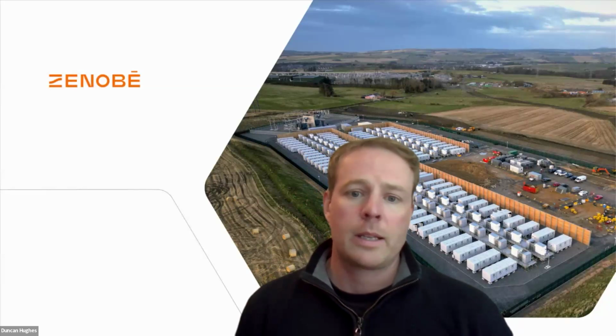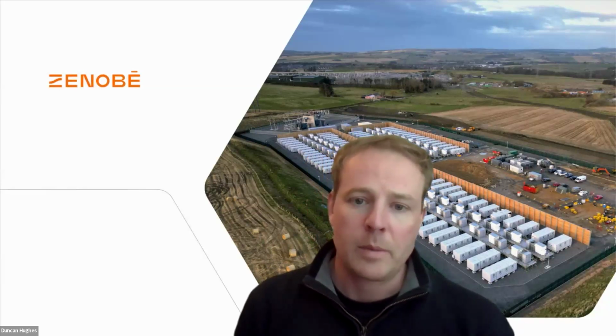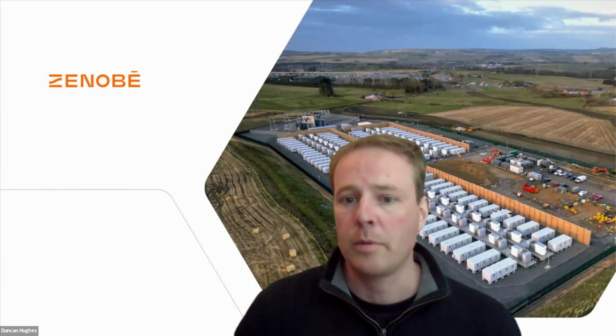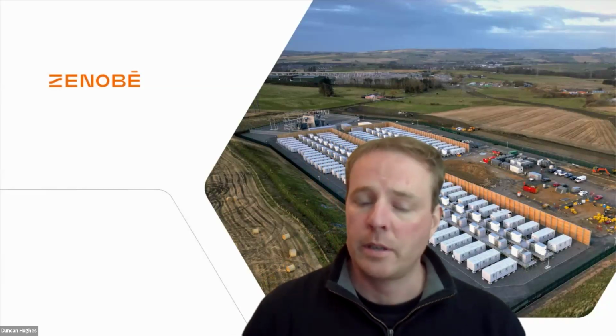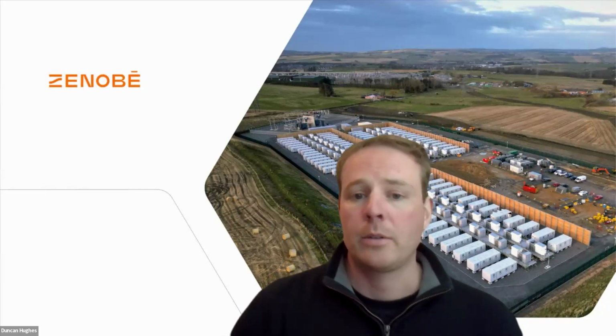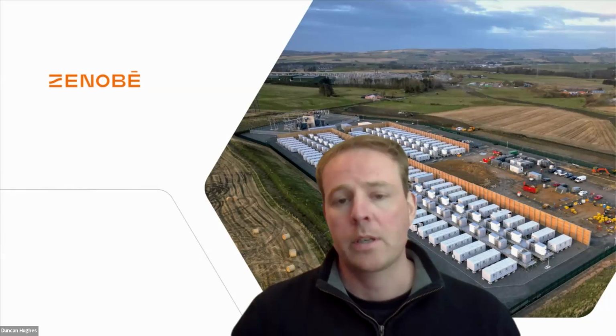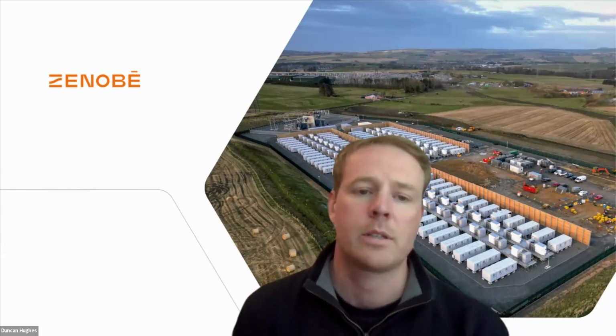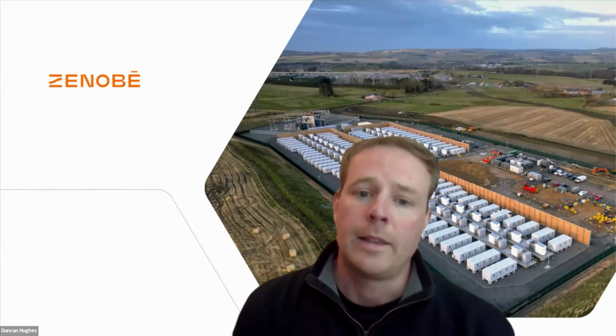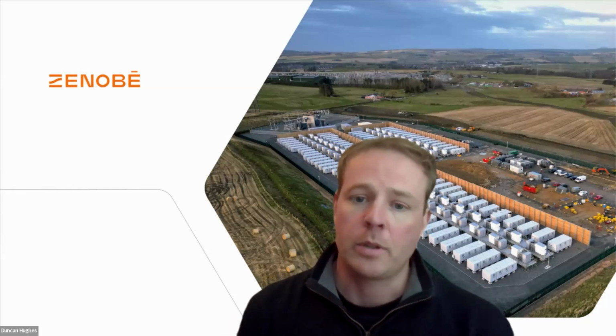One of the key things that lets us do that is the power plant controller that sits on top of it. The grid forming nature of the inverters is an inherent characteristic of that technology type, but how we put that together with the battery system and all the other services comes from the power plant controller, the GEM system, which Wartsila put together. We did a lot of work with Wartsila understanding what we wanted the system to do, how we wanted to do it, and what the grid code required, and that system put it all together.